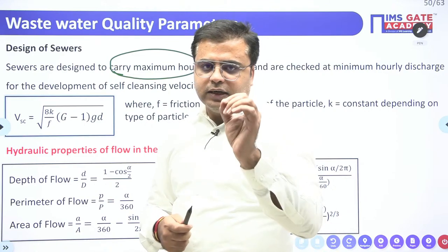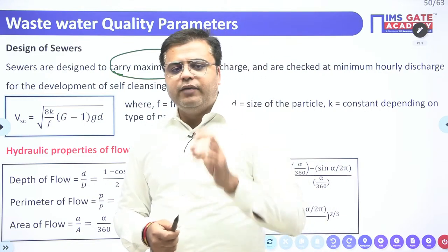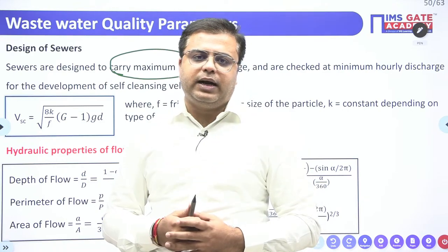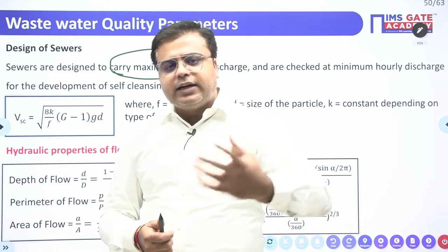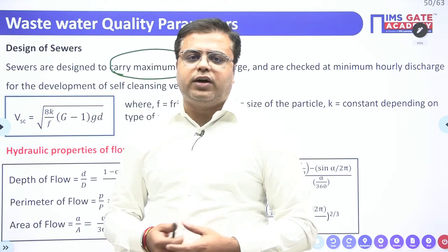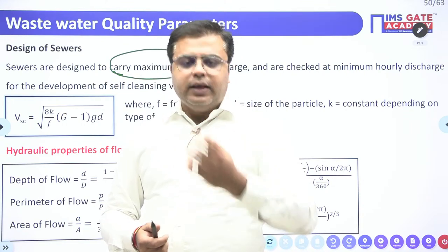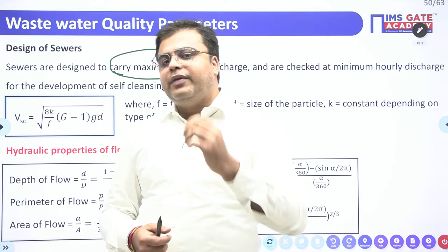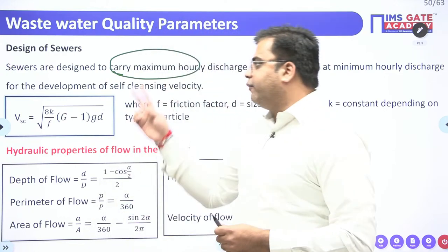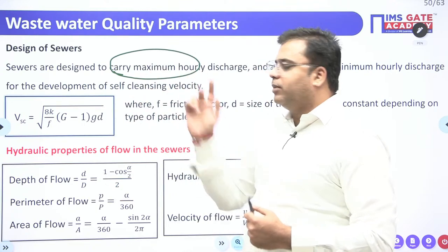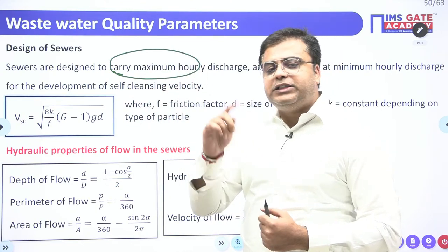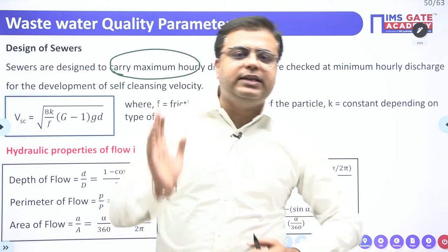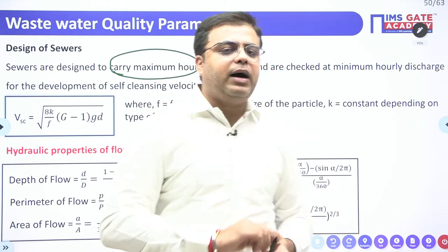Now, my dear students, understand this very well. When we talk about sewage, we are talking about a huge amount of suspended particles, right? So during the transportation of sewage or wastewater from one point to another, the settling of these solids will also happen, correct? So when we design the sewer, we design it to carry the maximum hourly discharge. But we check this sewer for the development of self-cleansing velocity during minimum hourly discharge.